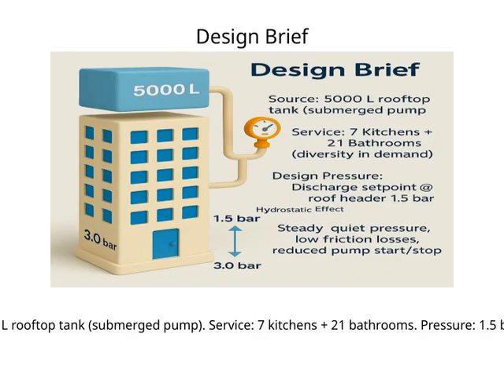Let's take a closer look at the design brief for this project. We are working with a 5,000-liter rooftop tank, which uses a submerged pump to supply water. The primary service points include 7 kitchens and 21 bathrooms, so it's a fairly large and complex system. A key requirement here is maintaining a pressure of 1.5 bar at the header. This is crucial to ensure that water flows efficiently and consistently across all these outlets. Overall, this brief sets the foundation for our design approach, focusing on capacity, service needs, and pressure requirements, all of which are vital to delivering a reliable water supply for the entire facility.